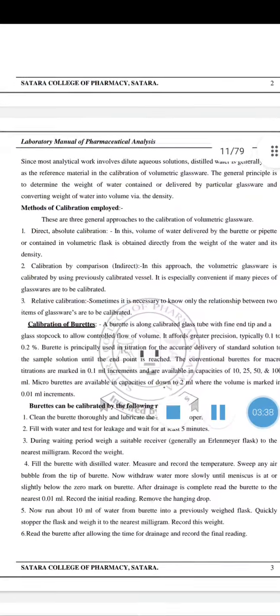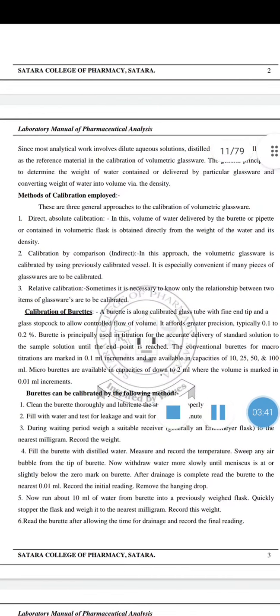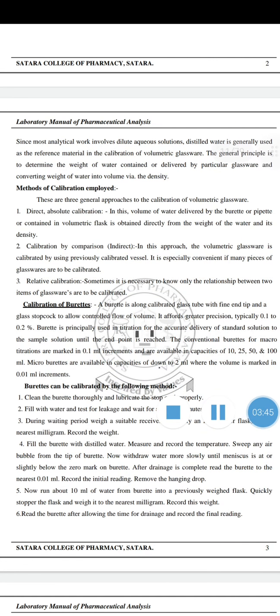Now the methods of calibration employed. There are three general approaches to the calibration of volumetric glassware: direct absolute calibration, calibration by comparison, and relative calibration. The first is direct absolute calibration, in which the volume of water delivered by the burette or pipette, or contained in the volumetric flask, is obtained directly from the weight of the water and its density. In calibration by comparison, the volumetric glassware is calibrated using a previously calibrated vessel. It is especially convenient if many pieces of glassware are to be calibrated. Then relative calibration: sometimes it is necessary to know only the relationship between two items of glassware.